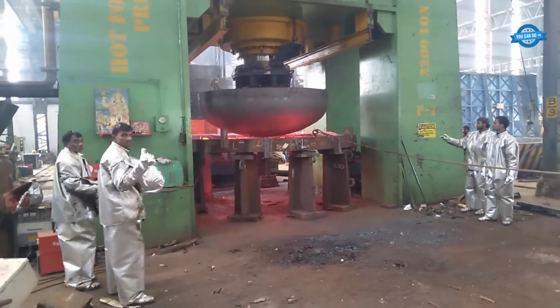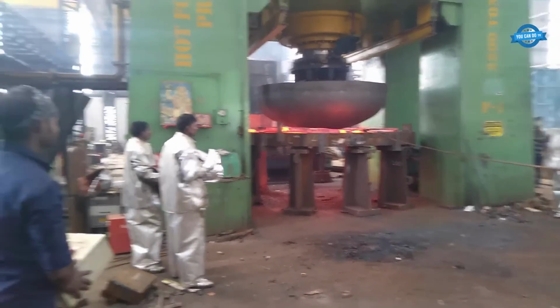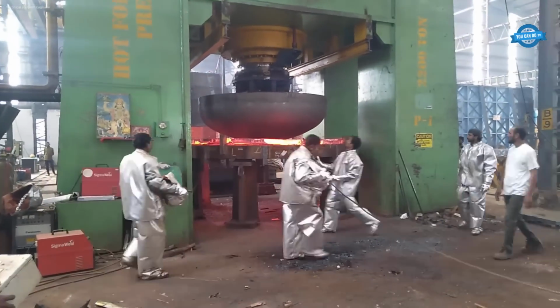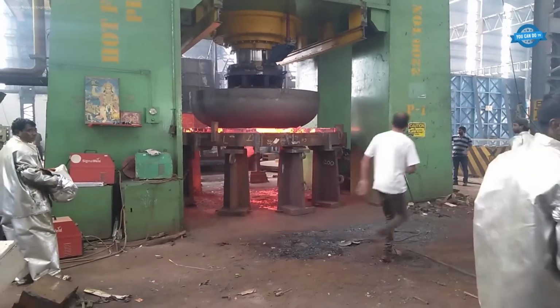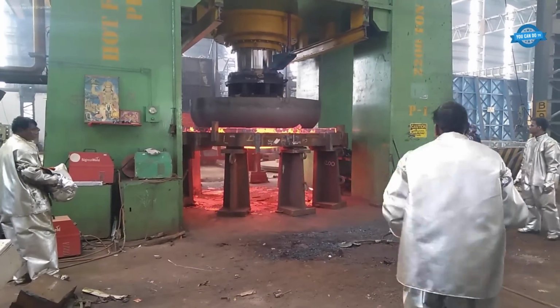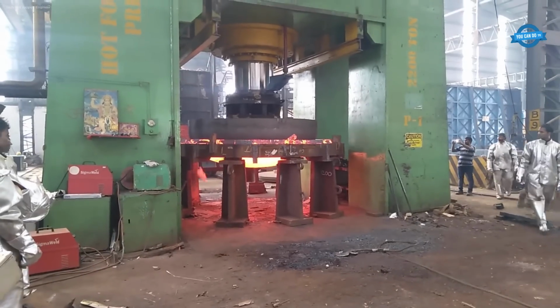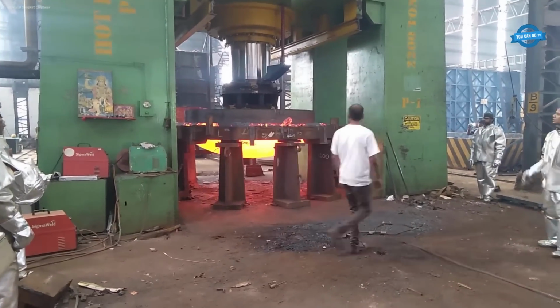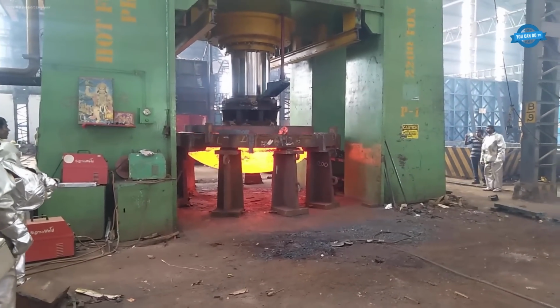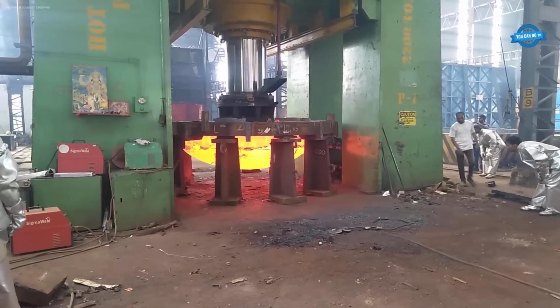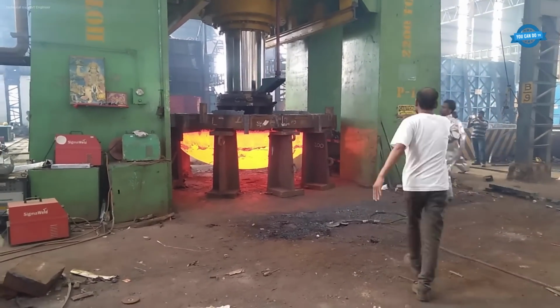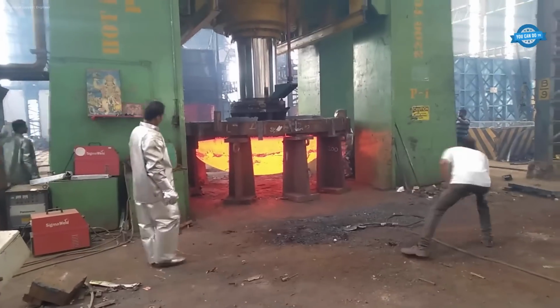In hot forming, the steel is heated to around 900 to 1000 degrees Celsius, increasing ductility for easier shaping. Hydraulic or spinning presses then mold the plate into torispherical, ellipsoidal, or hemispherical forms. This thermal process ensures uniform thickness, reduces internal stress, and improves mechanical properties.